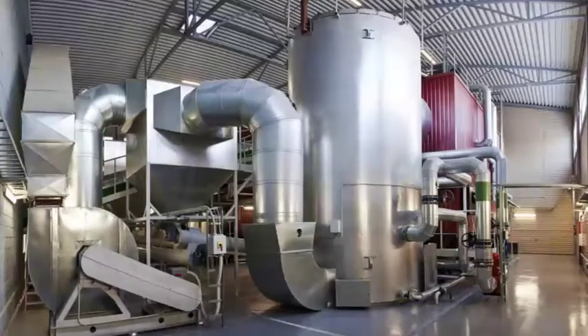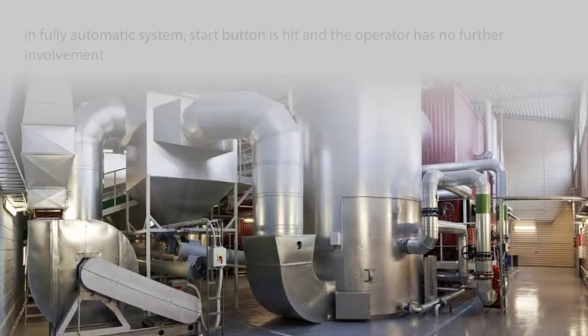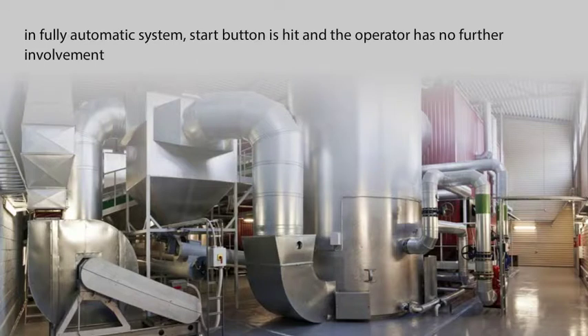The system might then be configured for someone to hit an igniter button, which would open a pilot fuel valve and start a spark igniter. It might then be necessary for a main fuel valve to be opened manually. In a fully automatic system, a start button is hit, and the operator has no further involvement. The BMS handles everything from start to finish.